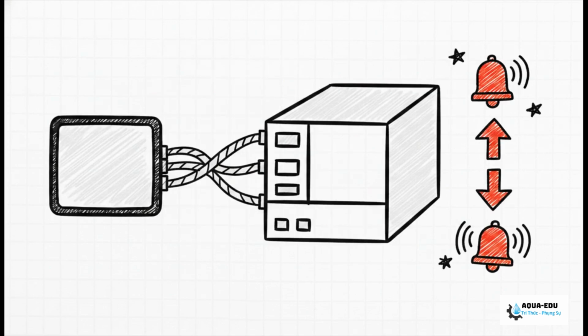For data integration, connect your shielded, twisted pair 4 to 20 milliamp outputs directly to your PLC's analog input module. And hey, if your specific architecture demands it, hook up the RS-485 terminal for Modbus RTU communication. Next, set your hard relay outputs. We need to trigger a high alarm at 0.5 milligrams per liter, that's our membrane danger zone, right?